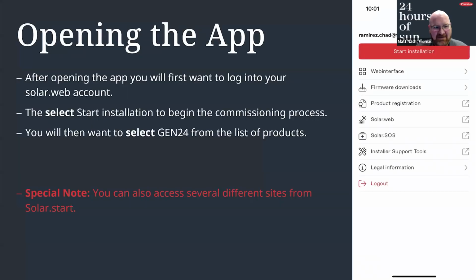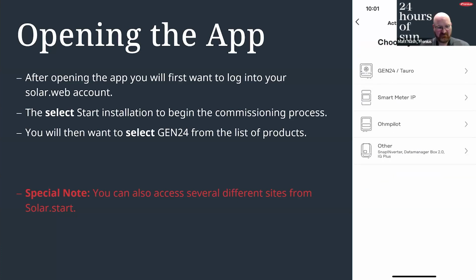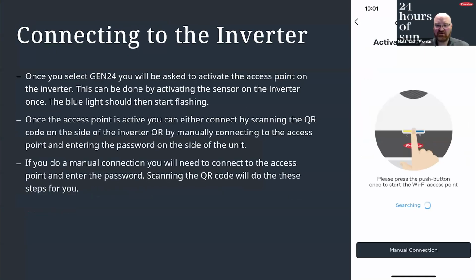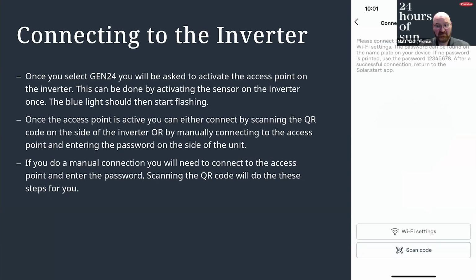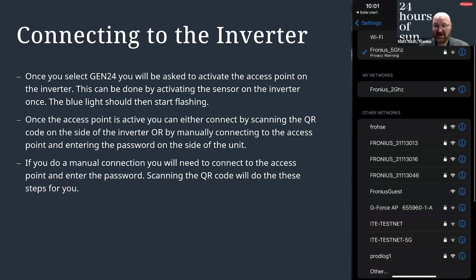Once you open up the app, you're going to want to log into a SolarWeb account. Next, you're going to click on Start Installation, and then select the Gen24. Then it's going to ask you to activate the access point for the inverter. You just tap the center button on the front, and it's going to start looking for it. You can also do it the old-fashioned way with a manual connection by selecting the Wi-Fi settings. You find the serial number of the inverter and put in the password, but that's really the hard way.